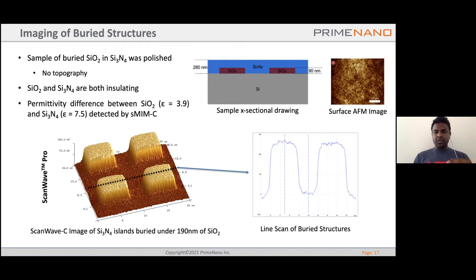And the topography, which is indicated on the right here, doesn't show anything. There is no topography that we can see. But in the ScanWave response, the capacitance response, you can clearly identify individual silicon oxide islands. Now, what is exactly happening is as the probe is scanning from left to right, it is seeing a difference in the capacitance, whether it's coming only from the silicon nitride, full 280 nanometers of silicon nitride, or the capacitance contribution because of the combination of silicon nitride and silicon oxide islands. That's the delta C that we're seeing here.